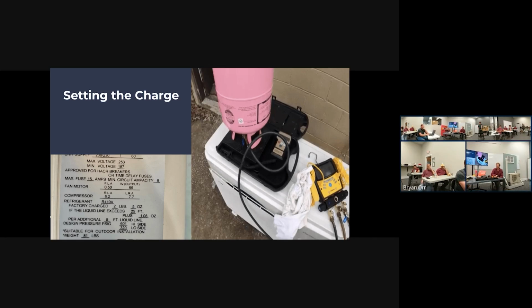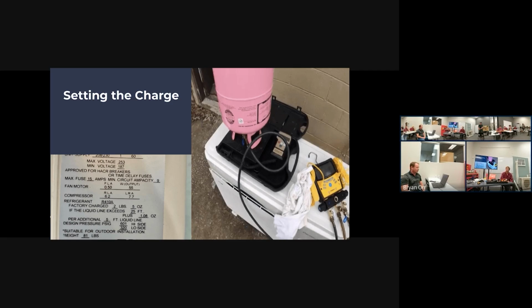Which is a reason why I don't like doing it how it's shown here with the big old gauge and multiple 6-foot hoses on it, because that makes it more difficult. I would rather see us do it with the shortest possible hose, probably one 6-foot hose or even a 4-foot hose, and a probe setup, so that way you're not having all that additional charge. Once you've bled your hoses, then reset your scale, and you have that ball valve right there, so you can open it up and anything happening on your scale is what's going in past that point right then. You shut the ball valve off, and then you've saved the refrigerant that's in your hoses. So you're not worried about that extra refrigerant going into the system. And then you won't be wasting extra refrigerant if you use a small line and just hook straight to the tank. But Aaron Ward has a question.